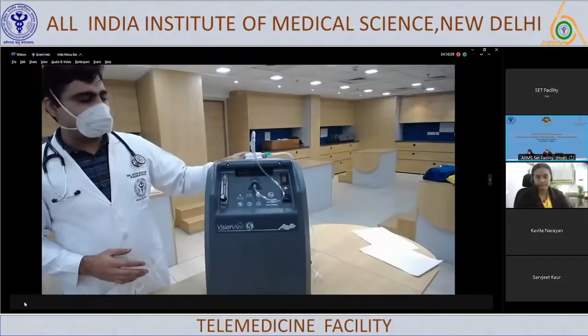A little bit about the maintenance. The maintenance includes external cleaning of the machine, cleaning of the humidifier water, and cleaning of the nasal prong. It should be done regularly, usually once a week for the machine and the tubing of the nasal prong, and the water should be changed almost daily or as required. The cleaning of the filter has to be done as per the manufacturer.